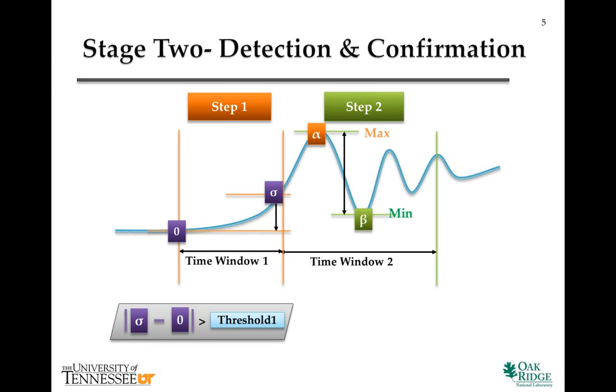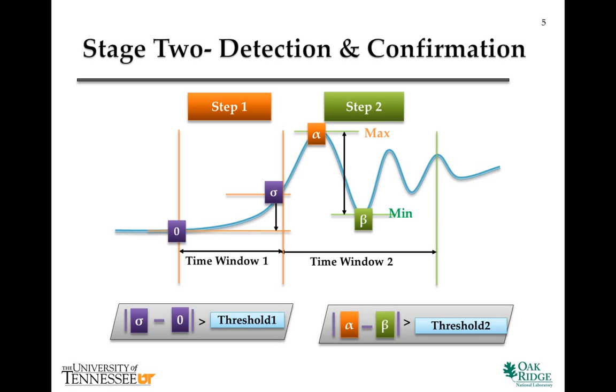The program will then proceed to calculate the maximum and minimum angle value over the second time window. If this difference is over a certain threshold in multiple units, the oscillation is confirmed.